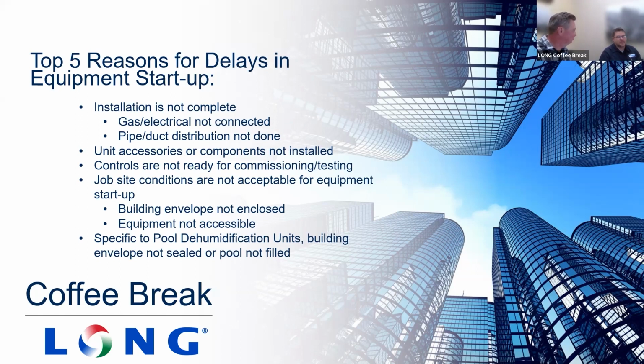Mm-hmm. If the building's not ready, the units aren't really ready. It's not the most ideal condition to use a very expensive rooftop unit as a temporary heating or cooling source, although we know it sometimes is necessary and happens. It's not the most ideal. You also don't want to not maintain that piece of equipment while it is started in a temporary application. You want to be able to change those filters on a regular basis and make sure that you're protecting that piece of equipment. So that falls into the job site conditions not quite being there.